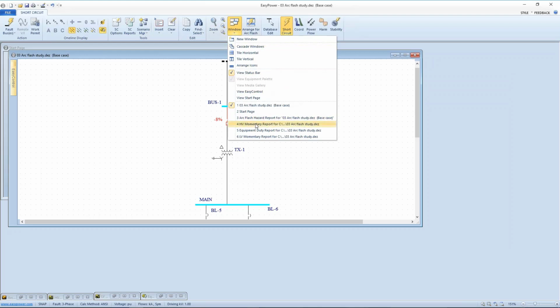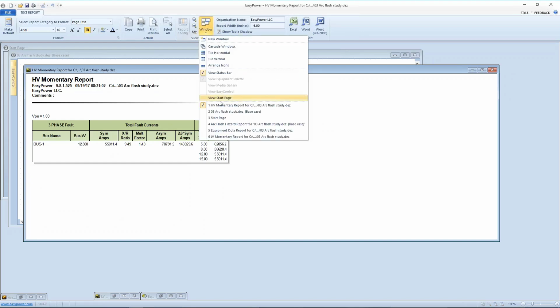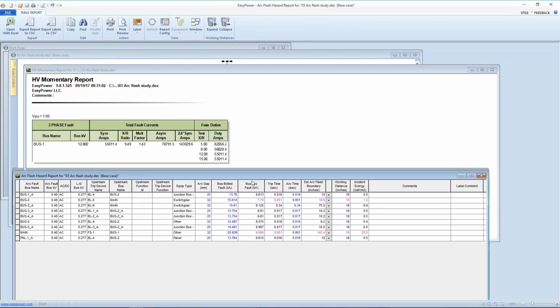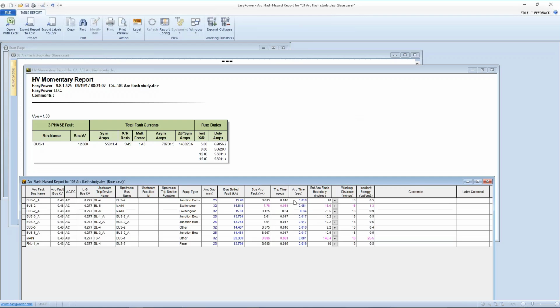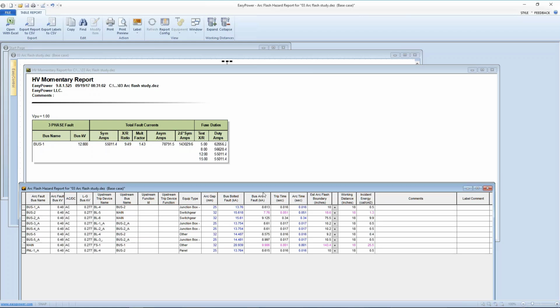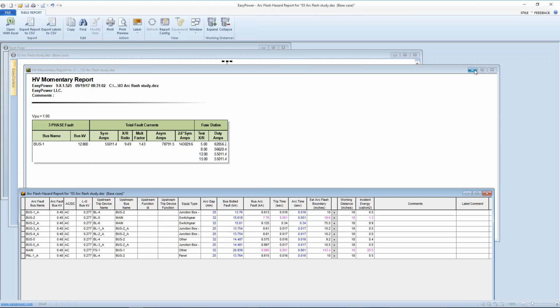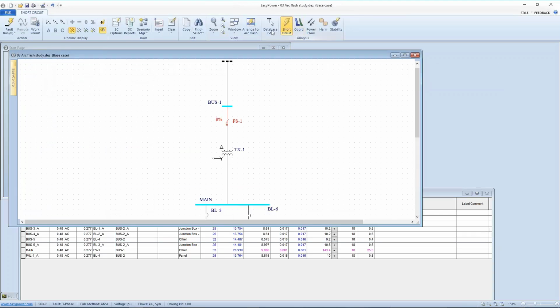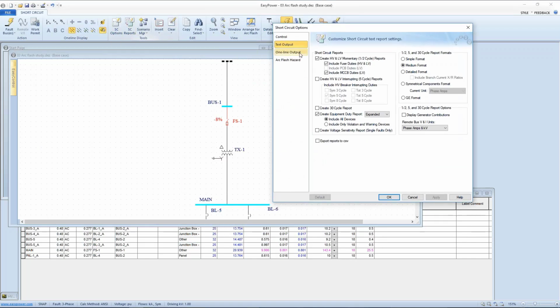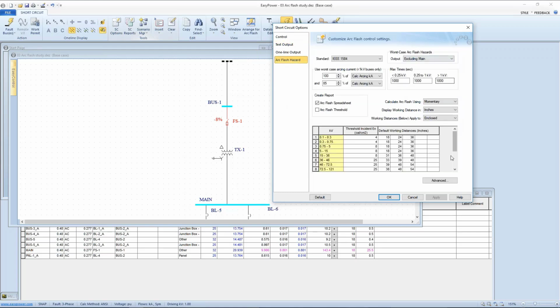Another report that I'd want to show is, so we'd have the same thing for my high voltage, and then we've been looking at, this is another requisite or required report referred to as the arc flash hazard report, and it shows the calculations that are being made at each point in the system, and consequently the controls that are being placed on the calculations. And I'm just going to refer to this briefly. When I'm in short circuit focus, I have available to me short circuit options in the EasyPower tools. One of the tabs is arc flash hazard, and this controls all the applications of the model that's being used for calculations. And again, in the documents that I used under reference, the IEEE 1584 is the de facto standard model that's used for arc flash, and these are the controls that are recommended or allowed in terms of applying what that model requires.